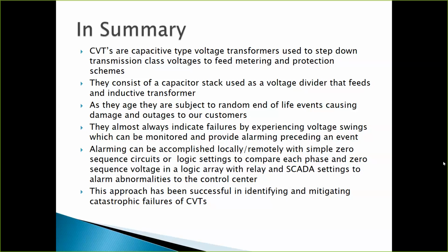It's for any type of disturbance or under voltage you may have system wide. So say your system experiences a fault down the road, the generator sees it, your voltage sags for a period of a few cycles. You don't want an alarm in that case. So we add a timer to that. Once that condition is satisfied, it has to hit that flip-flop timer for 1,200 cycles before it actually alarms. And that's how we overcome the unbalances in the system. So you're exactly right. We do that through a timer. All those outputs, the final path before it alarms is a timer. So thank you for your question.